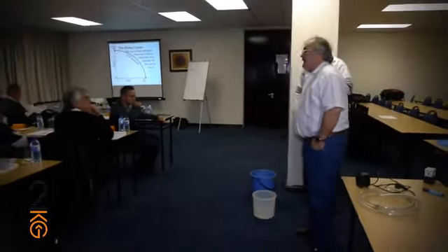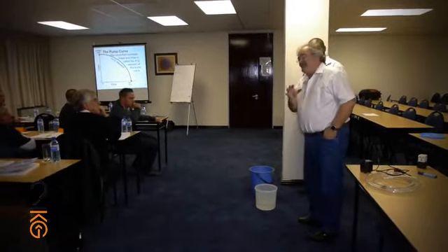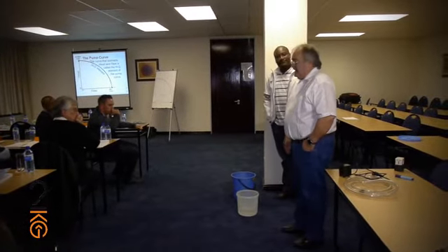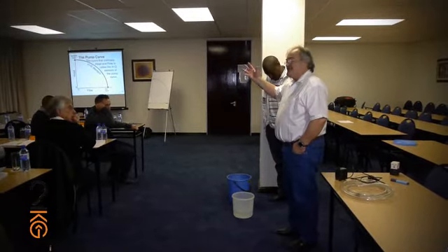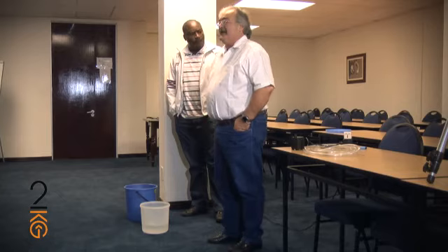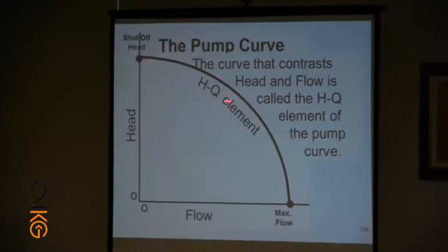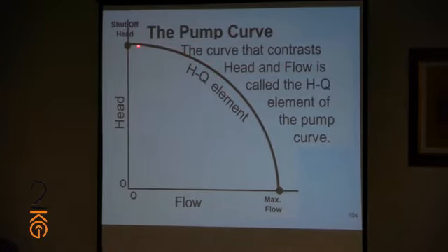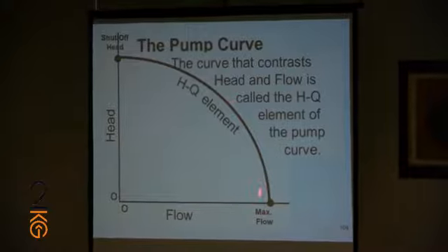All right. Many misconceptions about a pump. People have said to me, maybe you have some of the same thoughts. I'll talk about the pump moving on the curve and going into zones of vibration and high maintenance. Let's look up here at the board. So the pump should be operated right about here on the curve. We should avoid allowing the pump to run here. We should avoid allowing the pump to run out here on the curve.